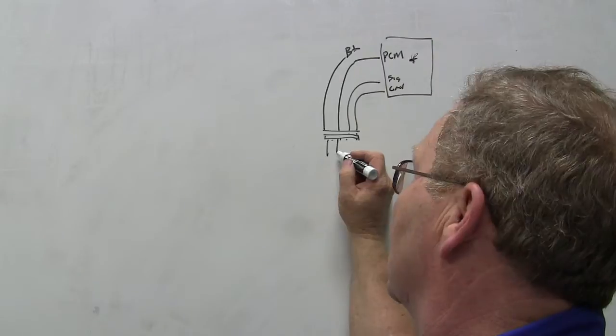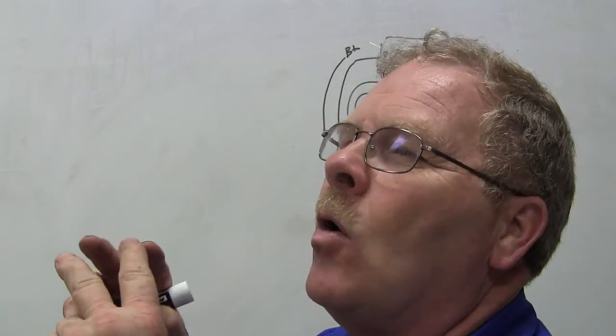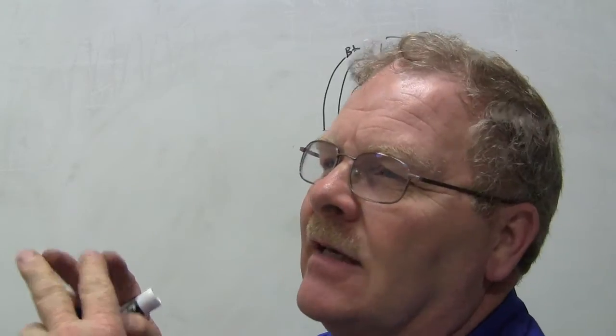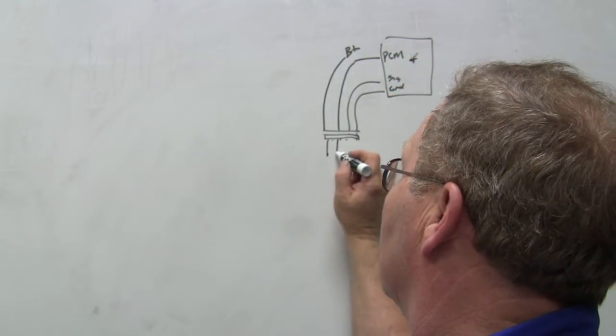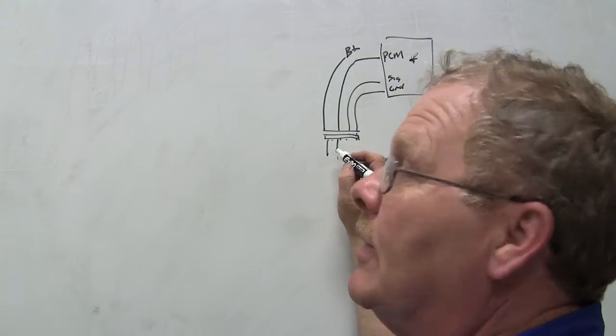A couple of ways you can check it. Let's say I measured the ohms of the two wires. They're supposed to be like 5 to 8 ohms or something like that. If you measure that and it's good, then you need to be looking somewhere else for your heater code issue. Well, I'm going to put a light bulb in here, like a fairly low impedance light bulb.